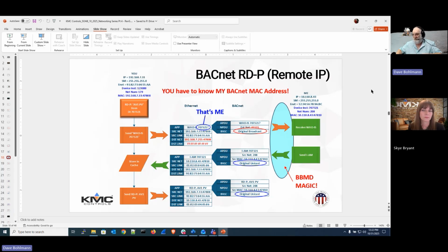A lot of people use other ports as well, but you have to at least support 47808, and by default that's what people usually use. But you don't have to. If you choose something else, you might run into other protocols that use the port number you choose. So you just have to be careful there. So it's kind of reserved, but it's kind of not.